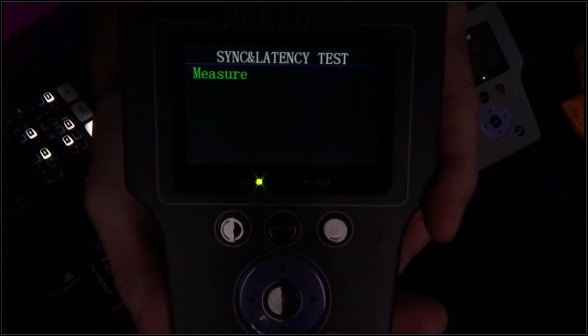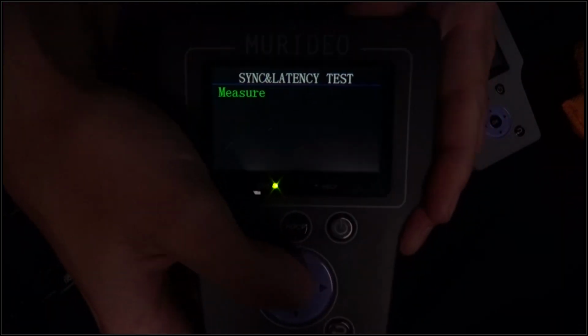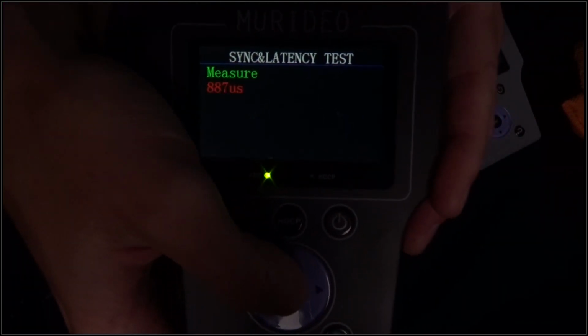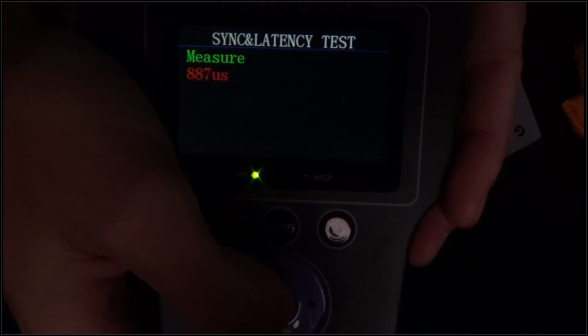Okay, we're at the sync and latency test. I'm going to press OK, and we're going to see this in microseconds. Right now we're at 887 microseconds, that's pretty fast. Remember, a microsecond is 1/1,000,000th of a second, so we're talking about 10 to the power of -6. We can see this at a very granular level. So the system latency between the source and the sink device, in this case the generator and analyzer, is 887 microseconds.